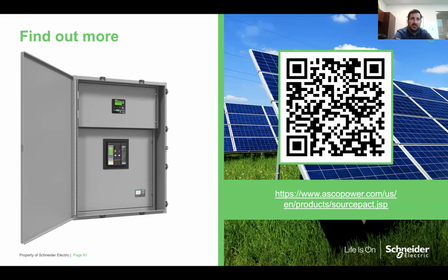So it makes sure that certain functions of the equipment that are critical for the safe operation within a larger system are well defined, tested, and implemented in a way consistent with these types of systems. For example, in UL 3008 and SourcePact, one of those points is you never want to connect two sources that are not synchronized to each other. For example, if the battery energy storage is still in grid forming mode and your utility returns, you cannot close that isolation device, the SourcePact, until either you're synchronized, which is out of scope for SourcePact, or until you know that the battery energy storage has turned off and gone back to grid following mode, and it's waiting to synchronize to the new source. So it's basically connecting to a dead bus. So the UL standard calls out requirements like that, and you must test and prove that you're meeting those requirements for safety. That way you're not implementing sequences that could knowingly be harmful to the overall facility.